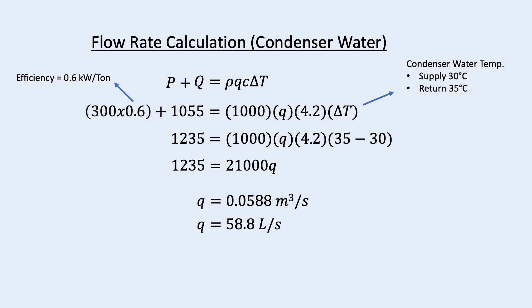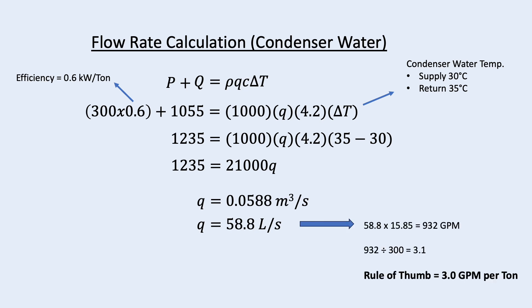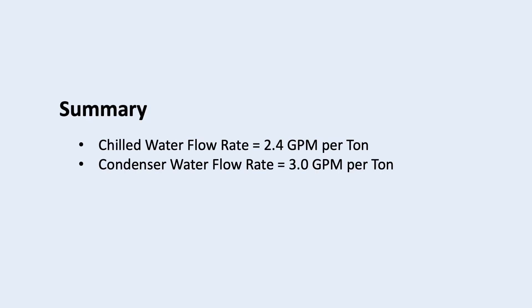Similarly, we can derive the rule of thumb for condenser water which is 3.0 GPM per ton. So, in summary, chilled water flow rate is 2.4 GPM per ton and condenser water flow rate is 3.0 GPM per ton.